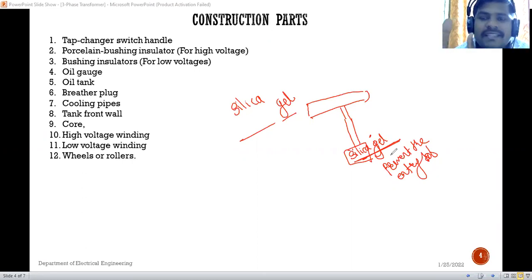बघा, बिग ट्रान्सफॉर्मर बघितला तर त्याच्या एका साइडला एक ब्रीदर असेल. सो त्याच्यामध्ये बघा वाळूचे खडे पण असतात. Okay, and there is silica gel that can be used. So air can be passed via that breather. म्हणजे एक्सपांड होणारी एअर ऑल्सो ॲज वेल ॲज ज्यावेळेस कॉम्प्रेशन होईल त्यावेळेस जी पास होणारी एअर आहे. So see, at that situation, the air passing should be dustless, or not ionized air, and it will prevent the entry of dust or moisture. Moisture ची किंवा dust ची जी काही एंट्री होणार आहे ती काय करेल, प्रिव्हेंट करेल. Right, no? लक्षात आलं? Function of breather.